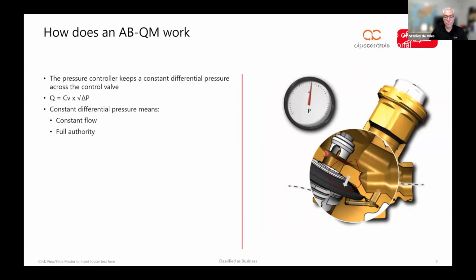So if we know how big the hole is and how much resistance it generates, and we know the differential pressure, we have the actual flow through the valve. If we are not messing with the control valve, so the CV value is not changing, and we also have a constant differential pressure, then we're basically multiplying two constants. And I don't think you have to be a math wizard to understand that two constants also generate a constant. This is how we always manage the same flow, and that means that we have a very predictable flow.